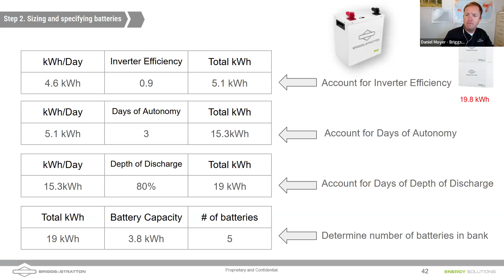So you're going to need 5 of our batteries in the top right corner, or a single stack of our 6.6 batteries in the top right corner, will give us 20 kilowatt hours. Actually the 6.6 will give us 19.8, a little closer to 20. So we figured out how many batteries we need.